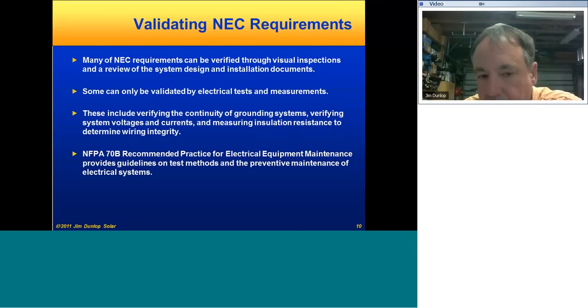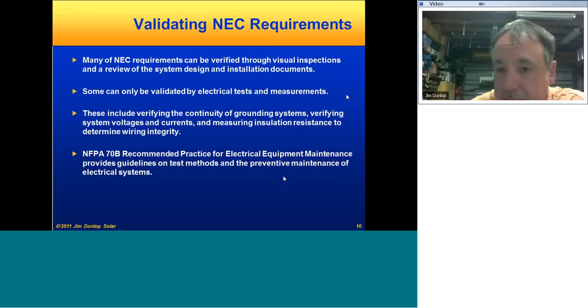And there's another reference here that I put, just the NFPA 70B, which is electrical equipment maintenance recommended practice from NFPA that talks about plant maintenance on normal electrical systems, which a lot of the same kind of stuff applies to PV as well. And PV particularly is exposed to a lot of pretty harsh environmental conditions, and it's probably more imperative that we test PV systems routinely than we do regular building electrical systems.